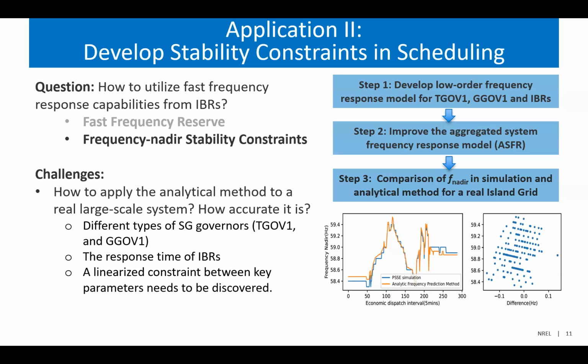And then we start to compare the frequency nadir in the simulation against our analytical method. As you can see here in the left figure, this shows how accurate the frequency nadir could look. The orange line is our analytical method. The blue line is the PSS/E simulation results. Amazingly, the largest error we got is around 0.15 Hertz. We think it's still acceptable, especially when you use it as a constraint in your scheduling stage.